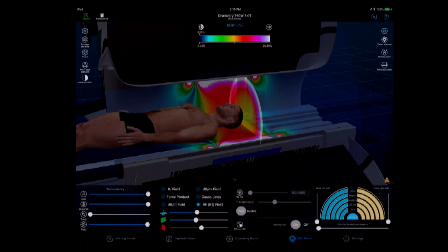We call those proximity burns. We didn't cover those today. Did you ever read where it tells you to keep your patient's tissues from touching the bore, keep them 5 millimeters, some say a quarter inch, some say a centimeter from the outer edge of the bore? Now you know why.